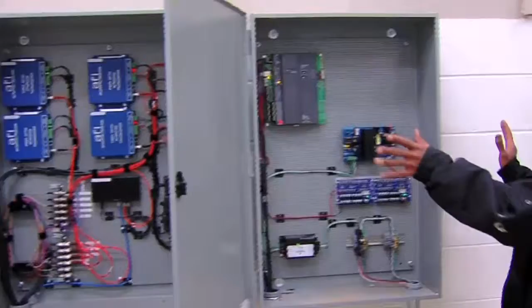This will be firing the locks when they install them on the 2 gate doors outside the yard. This is also powering our controller. This is a controller, very similar to what we have in the building, that controls doors, door contacts, and things of that nature. It's got all of the doors that are here: the 2 Sallyport doors, 108 and 109, the main gate to the yard, the black gate, which is door 110, and then the fence gate, which is 1G70. All 4 of those doors come back here.